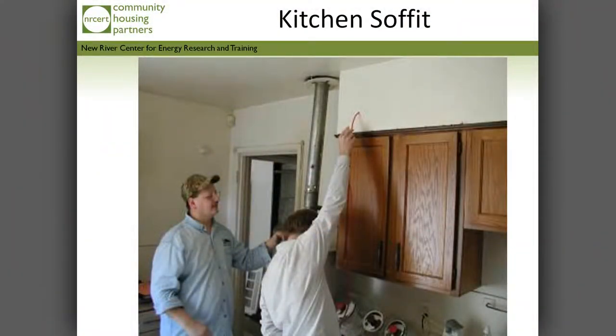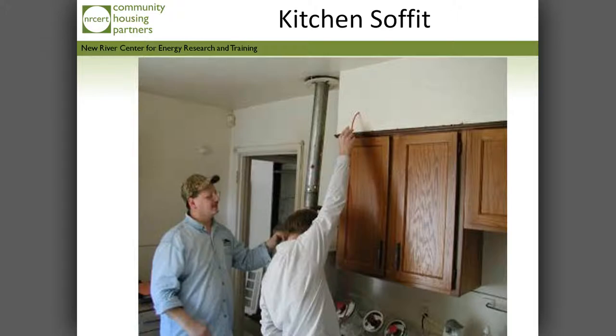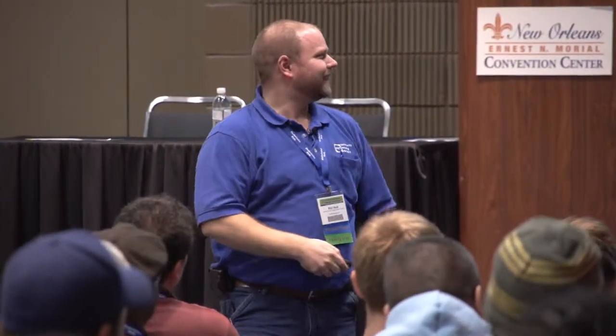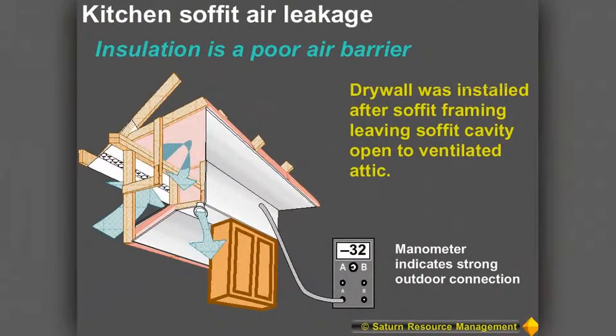Here we are testing in a kitchen soffit — or fur down, or bulkhead — basically over the kitchen cabinets. What should we get when we do a zonal test of this space? We should see zero, because we want that pressure plane, the air barrier, to be up at the top — not down at the bottom near the cabinets.